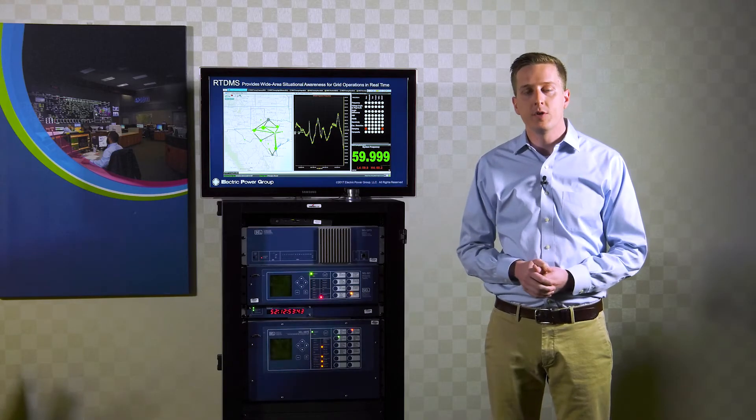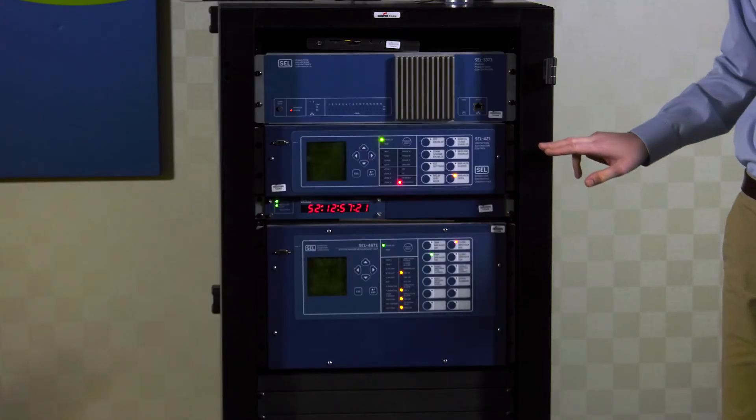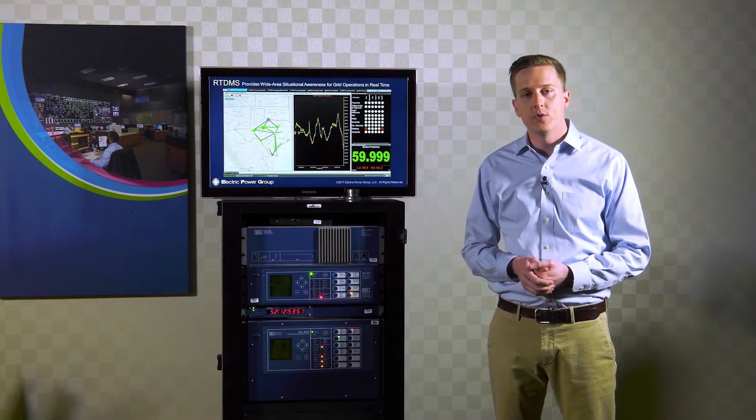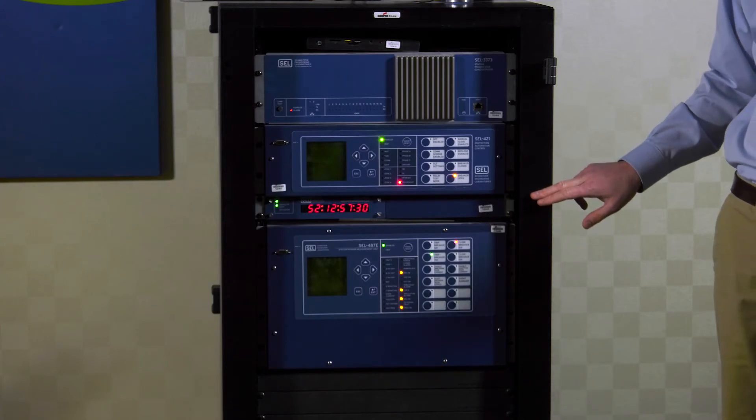Now let's take a look at a synchrophasor device here at PJM. Here we have two standard substation relays that receive signals from voltage and current transformers in the substation. We also have a high accuracy GPS clock that provides a time reference for measuring phase angle and to provide a time stamp on the measurement data.